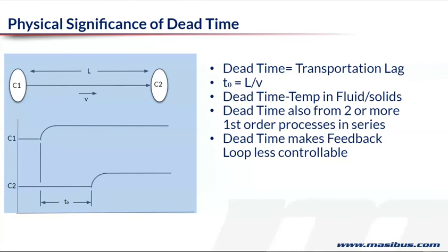Beyond some time, the PID algorithm is not good enough to control the process, and then you have to use some other algorithm. There are advanced process control and model driven PID, or sometimes you have to use a combination of a feedback controller and a feed forward controller. That also we will see today, what a feed forward controller is. But a simple PID controller, when the dead time is too much, is not good enough.